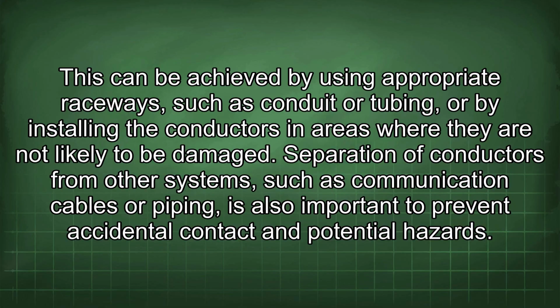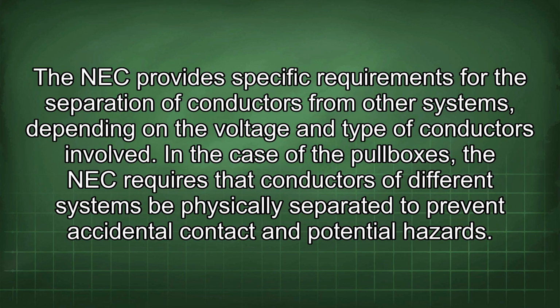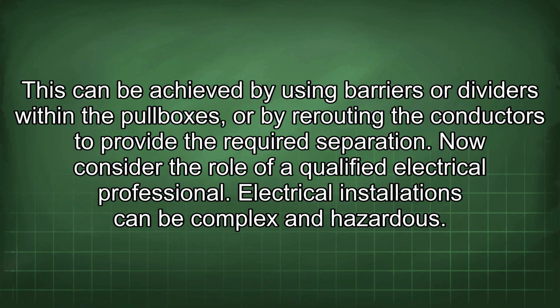Separation of conductors from other systems, such as communication cables or piping, is also important to prevent accidental contact and potential hazards. The NEC provides specific requirements for the separation of conductors from other systems, depending on the voltage and type of conductors involved. In the case of the pullboxes, the NEC requires that conductors of different systems be physically separated to prevent accidental contact and potential hazards.